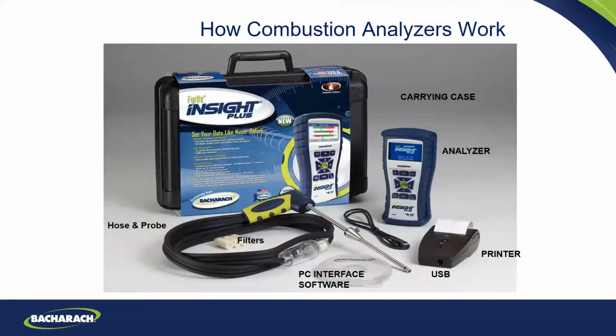At this time, it's going to calibrate that oxygen sensor, because Mother Nature always gives us 20.9% oxygen in room air. And then it's going to maybe zero the CO sensor if you're not in manual mode. After that 60 seconds, it's going to come up, and then you put the probe in the stack. You hit run, and you're going to be reading your readings.